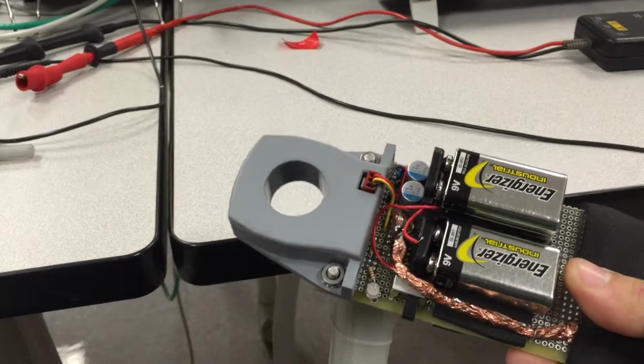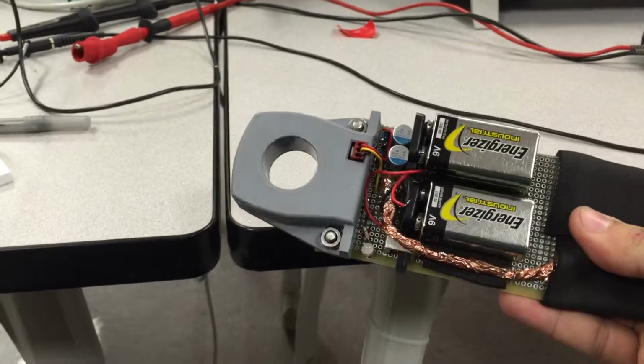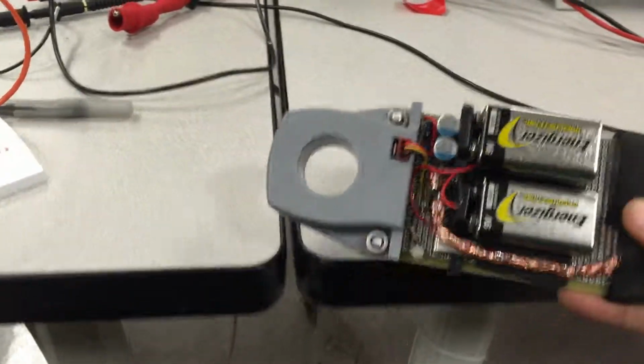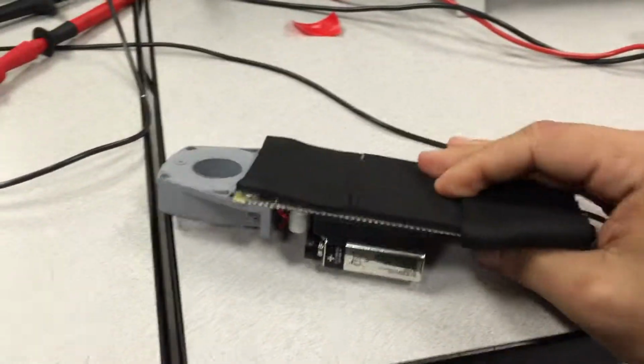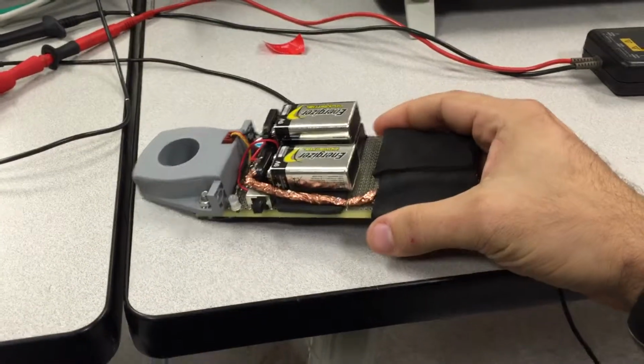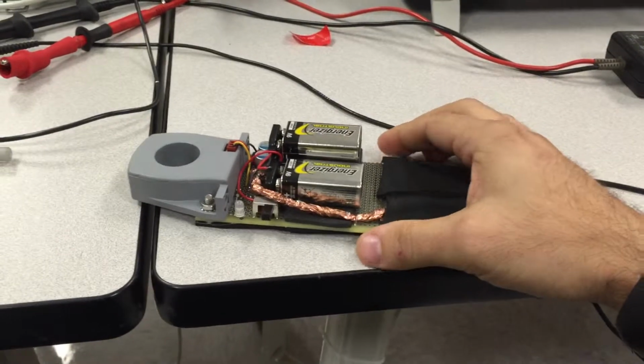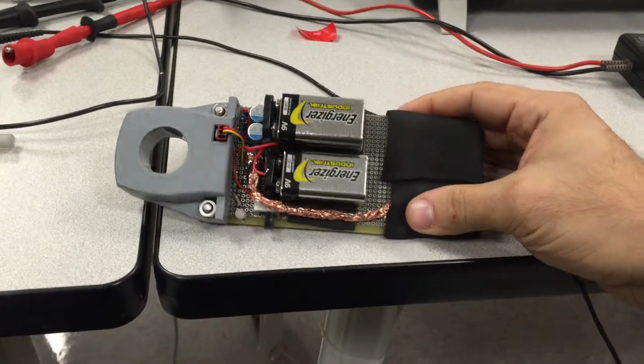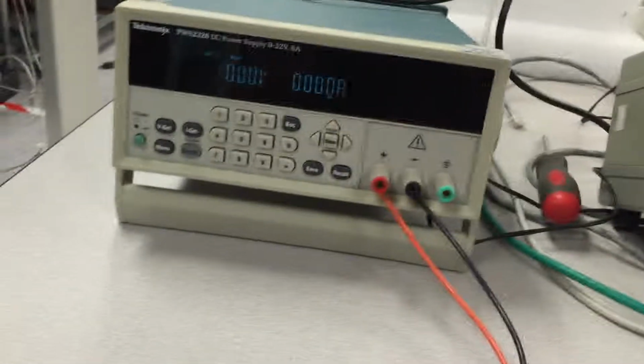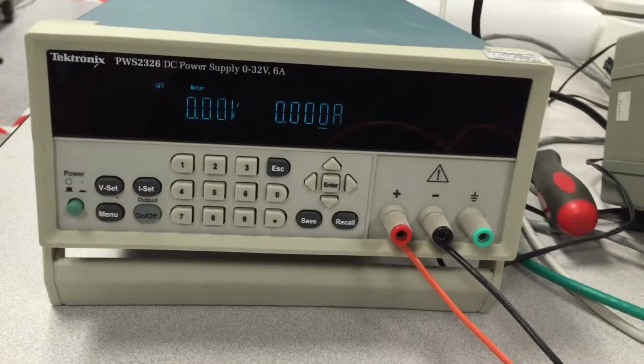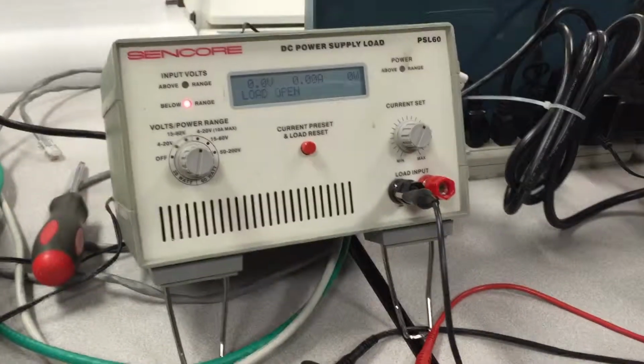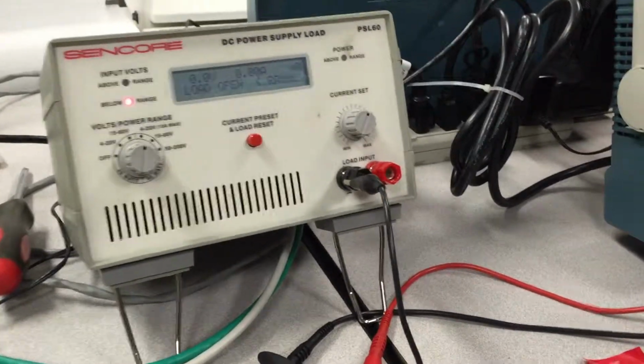It measures up to about 500 amps. So we're going to do a quick calibration check on it and set the scope up to measure current. The first thing we need to know, since this is not a calibrated probe, is what the conversion from current to voltage is, since we're using a voltage input on our oscilloscope to measure the output. So we're going to use a calibrated power supply in conjunction with a dynamic load to measure this probe sensitivity.